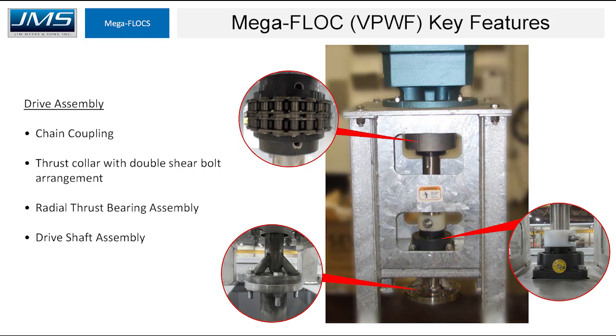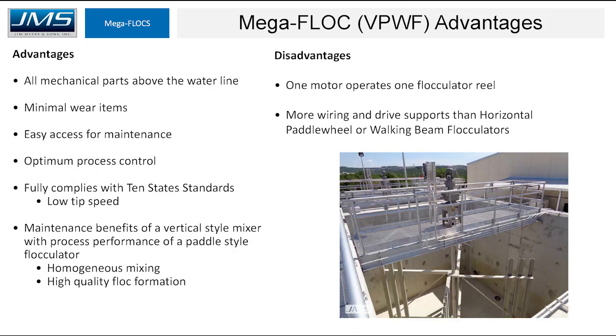Moving on to vertical paddle wheel flocculators. The drive assembly uses a chain coupling connecting to the output shaft of the gearbox. A thrust collar takes up all axial loads heading into the gearbox, and the radial thrust bearing takes up radial loads, which can significantly increase the lifespan of the gearbox. All mechanical parts are above the water, minimal wear items, easy access for maintenance, optimum process control with speed adjustment, and it fully complies with Ten State Standards with a low tip speed. You get the maintenance benefits of a vertical style mixer with the performance of a paddle style mixer.